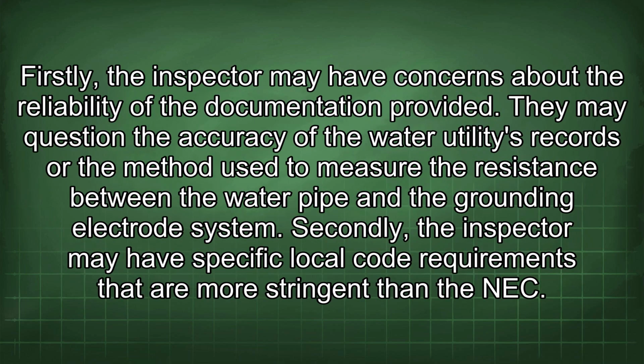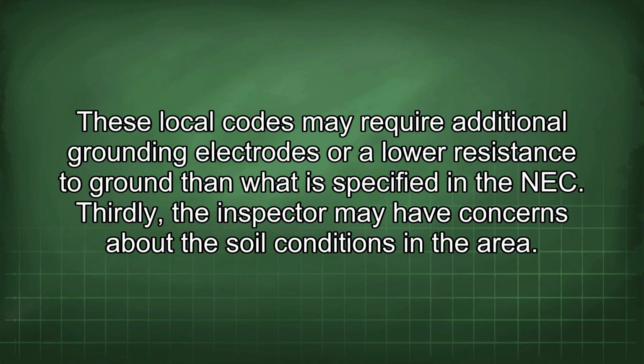Firstly, the inspector may have concerns about the reliability of the documentation provided. They may question the accuracy of the water utilities records or the method used to measure the resistance between the water pipe and the grounding electrode system. Secondly, the inspector may have specific local code requirements that are more stringent than the NEC. These local codes may require additional grounding electrodes or a lower resistance to ground than what is specified in the NEC. Thirdly, the inspector may have concerns about the soil conditions in the area.